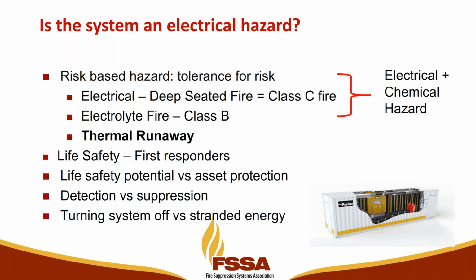Probably one of the most important concepts here is to understand really what we're dealing with from a fire standpoint. An electrical fire is considered Class C. An electrolyte fire - that's the components inside the battery - is a Class B fire. And then there's this concept of thermal runaway, which really doesn't fall under either.